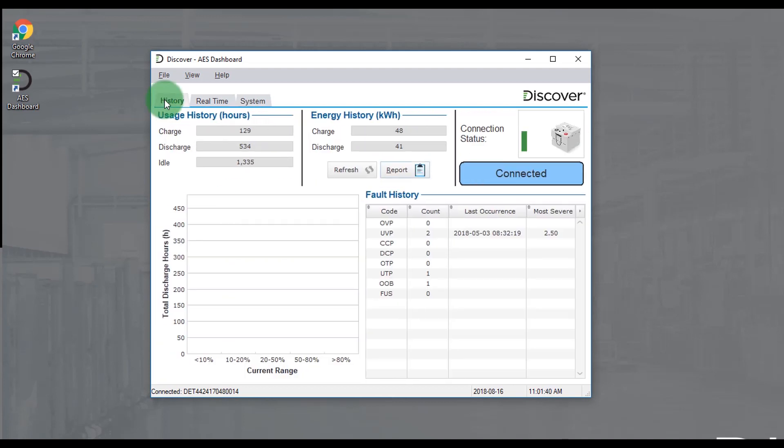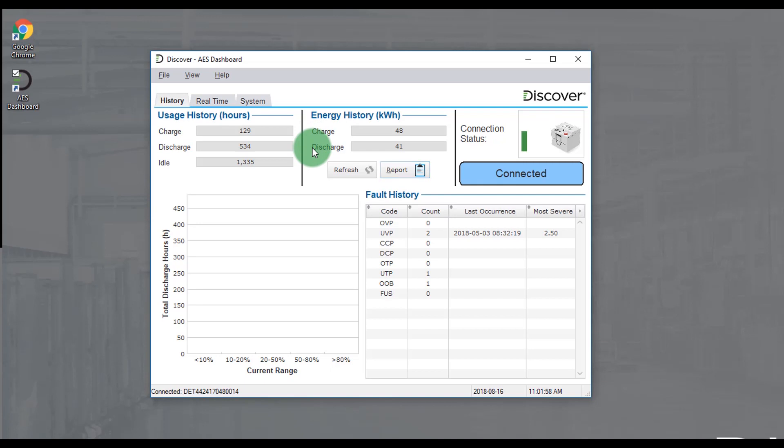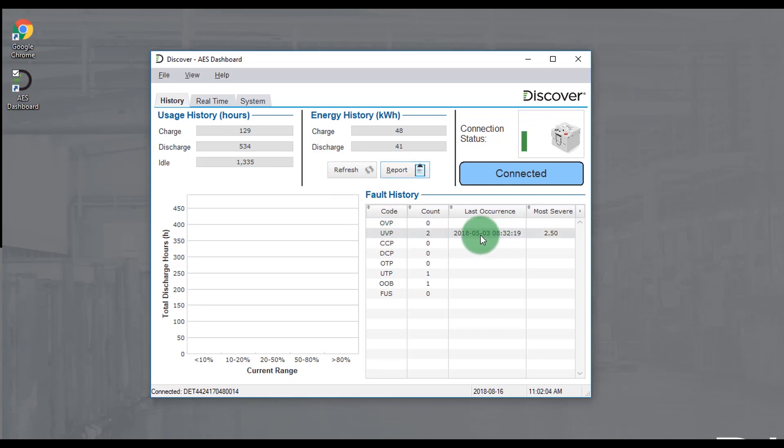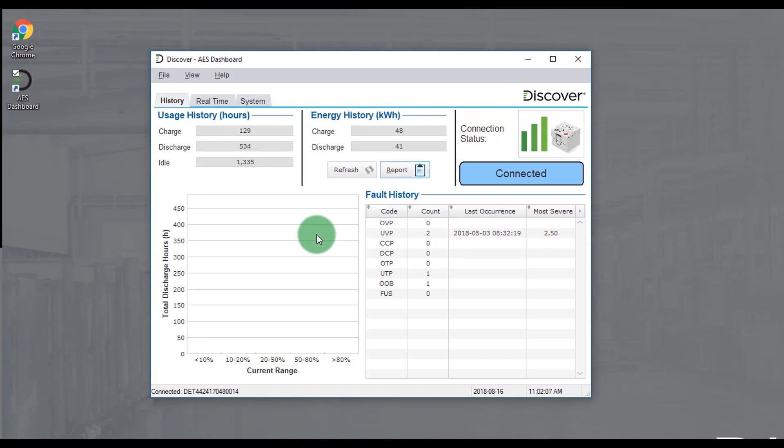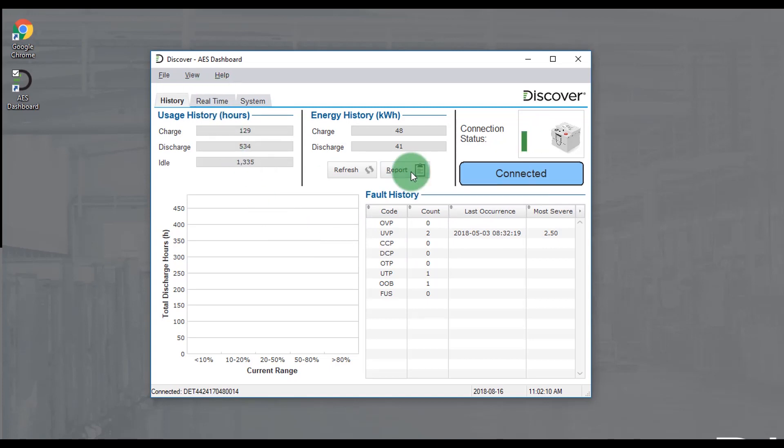In the history tab the total hours of charge, discharge, and idle can be seen for the battery as well as total kilowatt hour charged and discharged. There's also a list of fault history so we can see how many times a particular fault happened, when it last happened, and what the most severe value was. You can also generate a report to capture this data and print out.